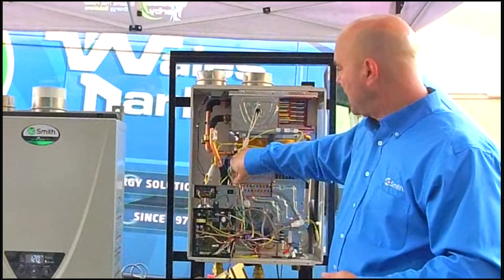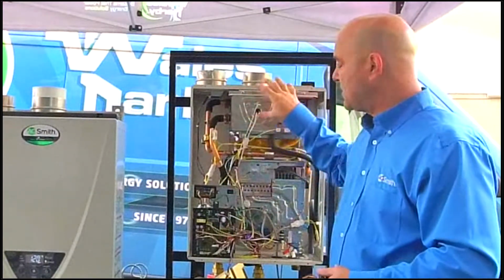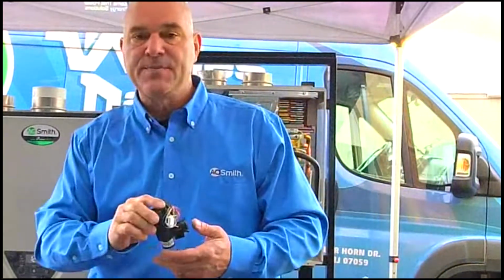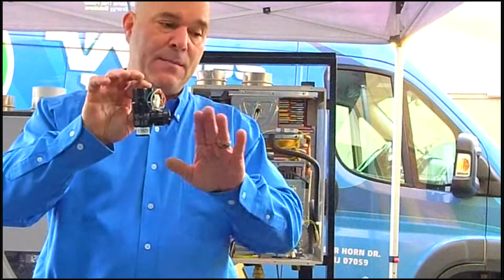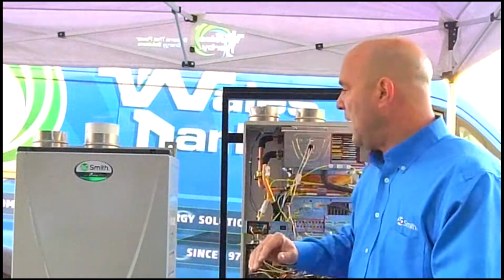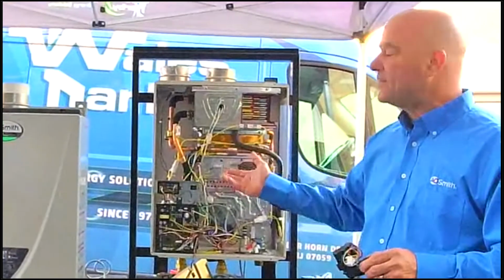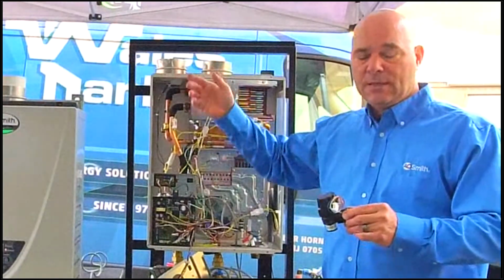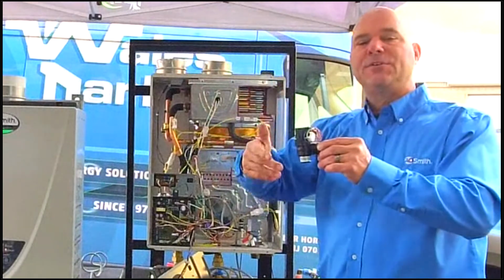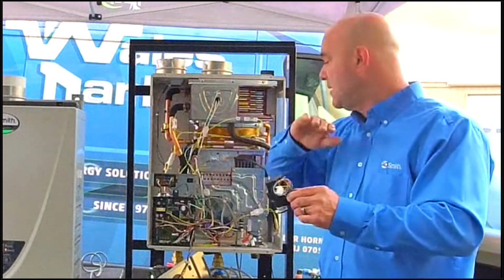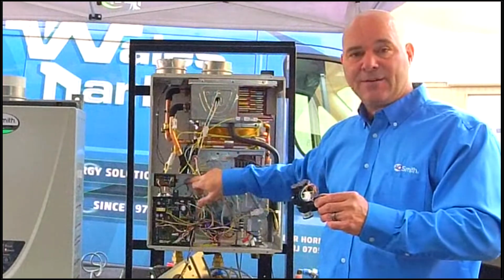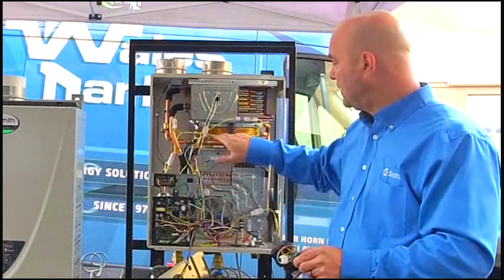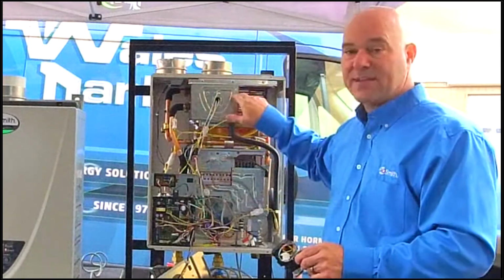We have an override that clicks on the thermistor on the heat exchanger. So we're taking some temperatures of the water as it's flowing through the heat exchanger, and this may open a little bit and mix some cool water in if we're over target, or it will close and allow it to run at normal. If you're working on an A.O. Smith ATI 540 and you want to flush the heat exchangers, you have to elevate the target temperature up to 140. At 140, you'll get this valve to open. After you get that valve to open, when you hit 140 degrees, shut the unit down right here. Shut the unit down. This will stay open, and then you'll have the ability to flush the primary heat exchanger and the secondary heat exchanger.